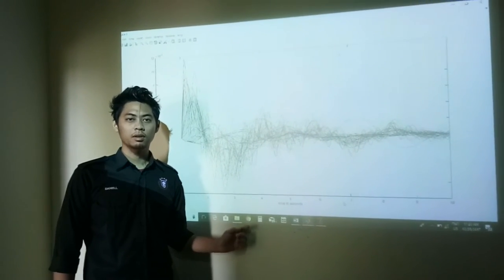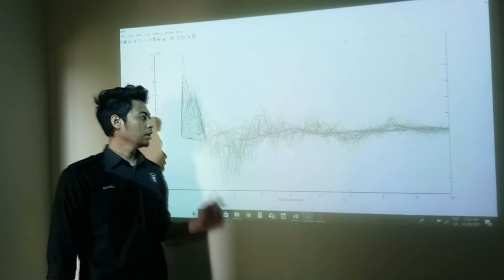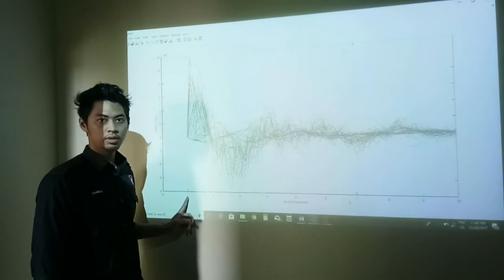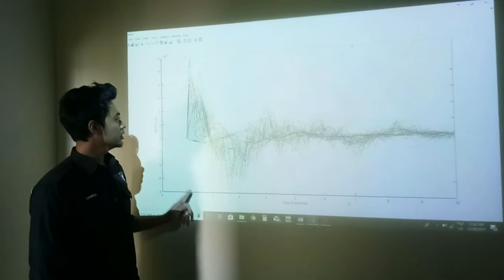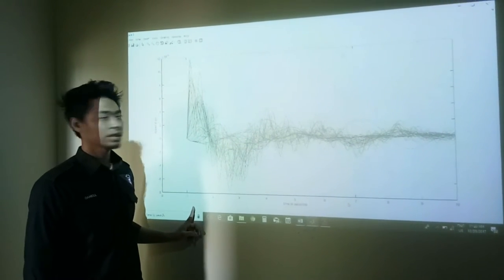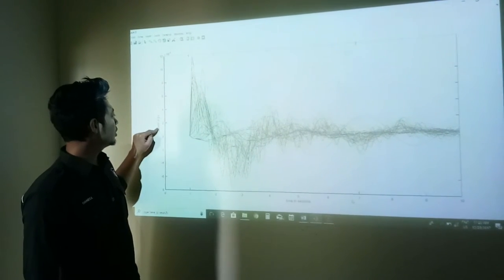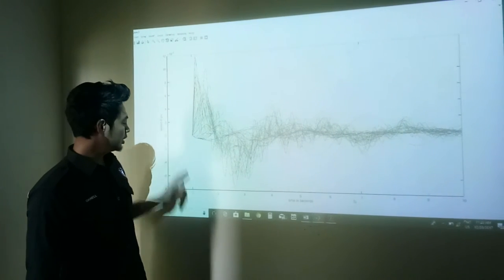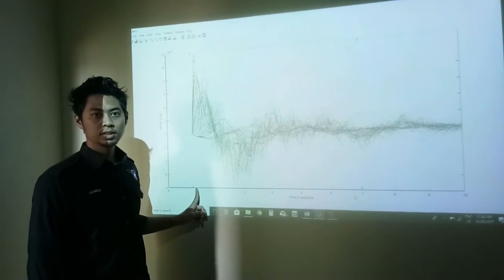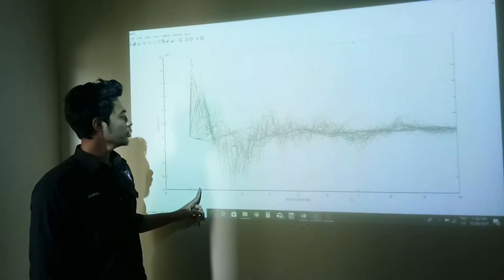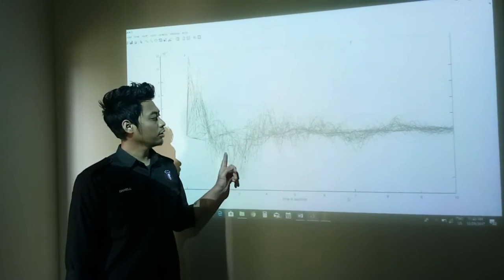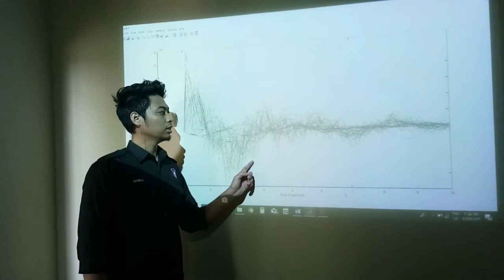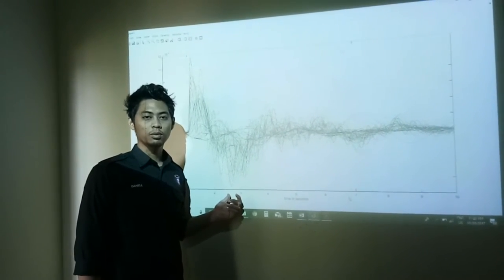For the third result of the stable case studies, we can conclude the simulation. After we start the simulation for one second, the result appears at 1.16 seconds, showing the rotor speed of the generator in per unit. As we can see, after 1.16 seconds, the graph goes to a stable condition. This is because our fault clearance is after 1.16 seconds.